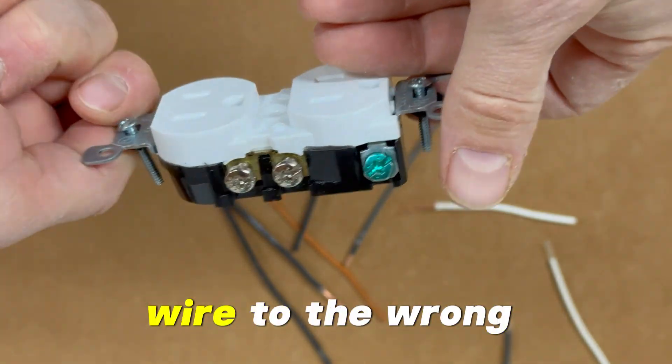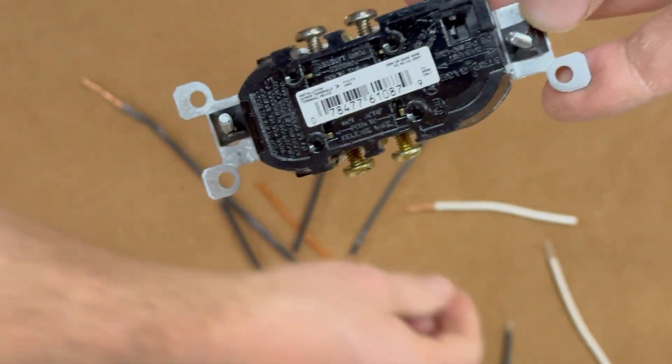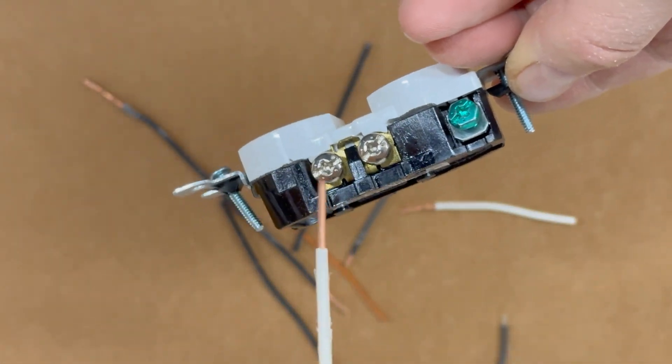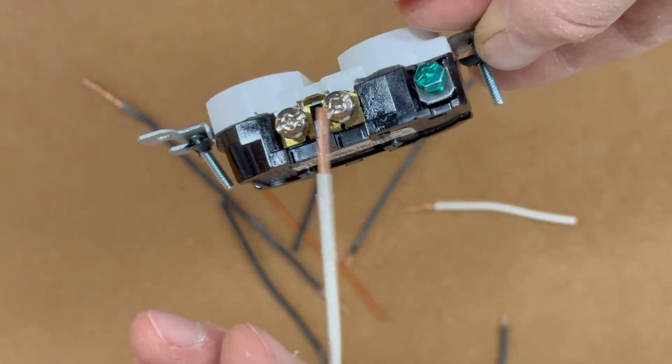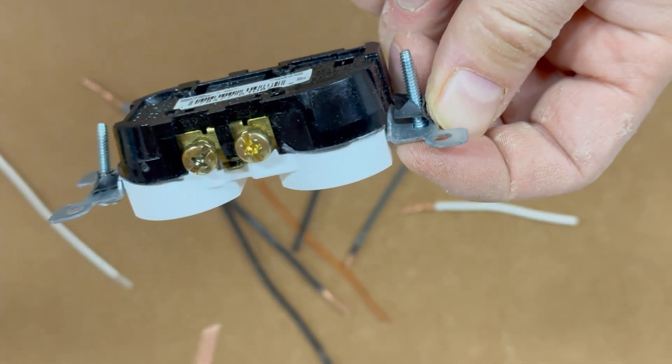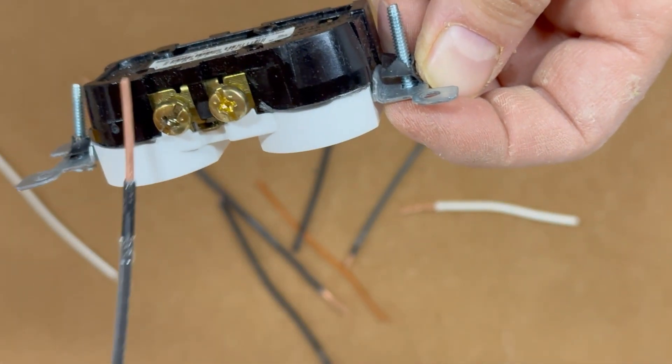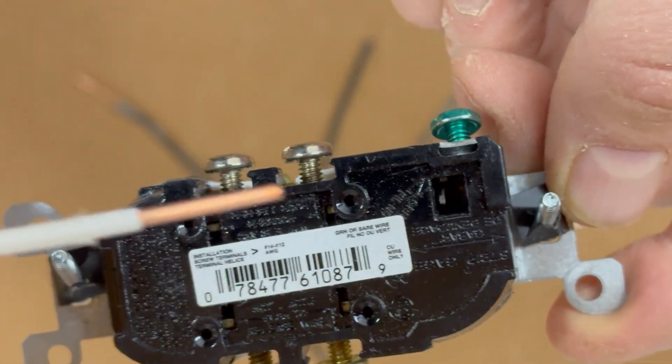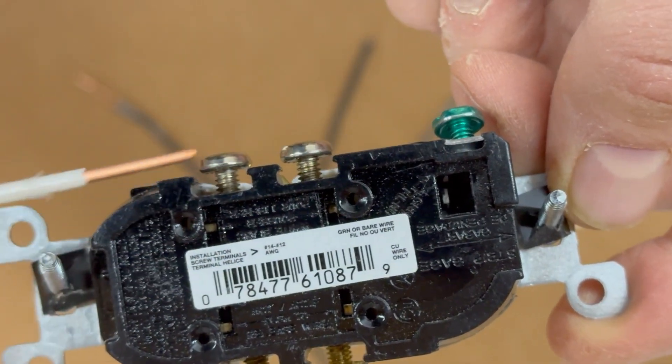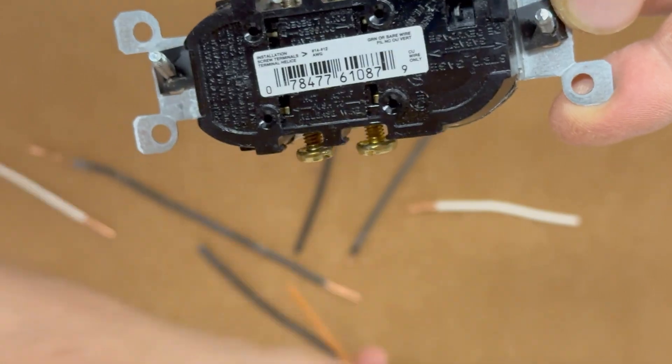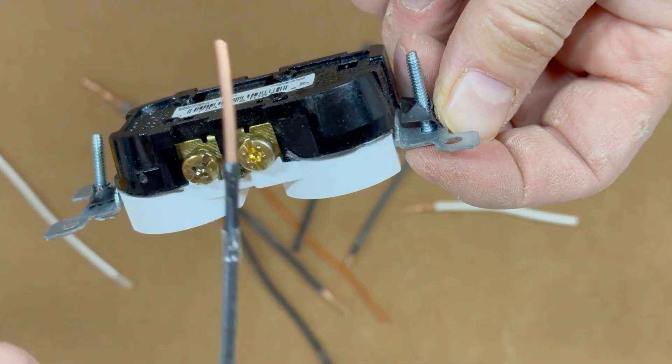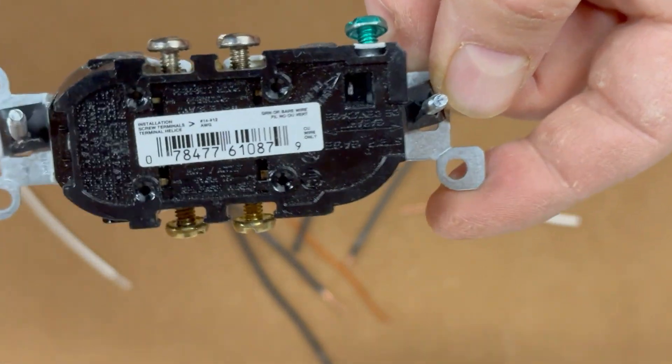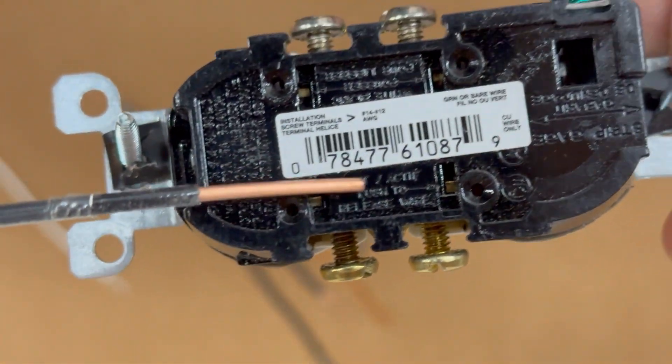Connecting the wrong wire to the wrong terminal. If you take a close look at an outlet, you will notice that the screws on one side are silver, while the screws on the other side are brass or goldish in color. It is important to remember that the silver screws are always connected to the white wire, also known as the neutral wire. The brass or goldish screw should always be connected to the black wire, which is called the hot wire.